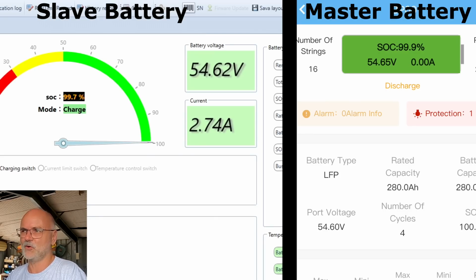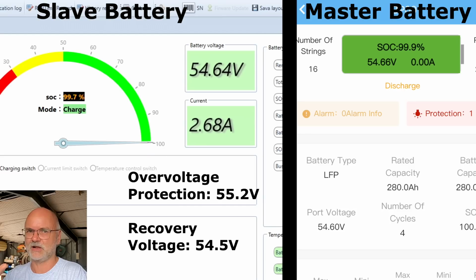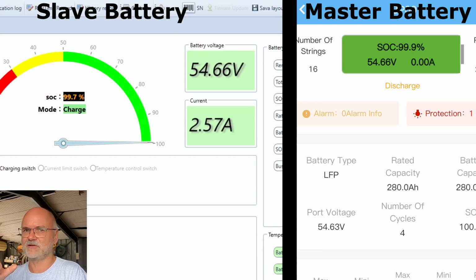This is a problem occurring if you change the settings to a higher voltage delta between disconnecting charging and reconnecting charging, the recovery voltage. You can see a quite large delta between the 2 battery packs then, but at the moment it will neither charge nor discharge. It leaves everything to the slave battery, and this one is microcycling again.